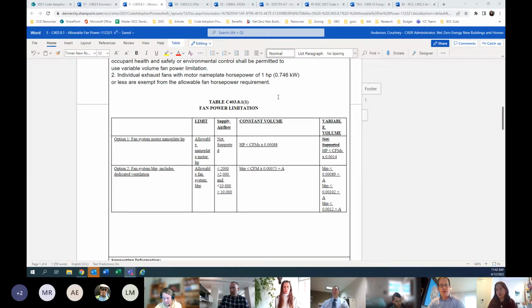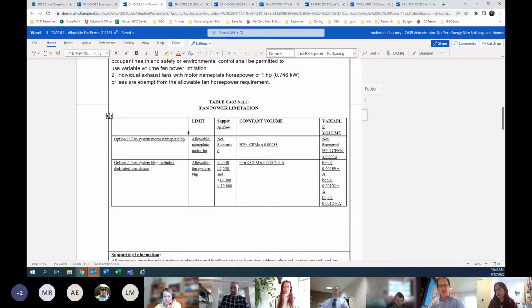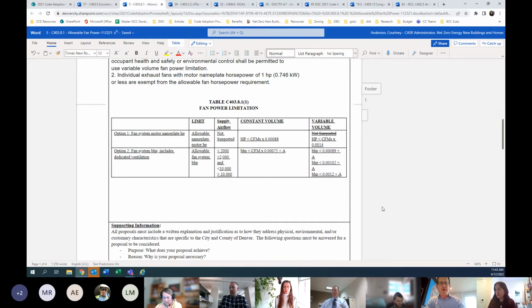So there's still two options. One is just the nameplate horsepower option 1, and there's the allowances there for constant volume and variable volume, and then option 2 is based more on the actual brake horsepower calculation, so the actual duct layout for the building. We have different allowances for variable volume systems. Recognize that the larger systems might have a different need than smaller systems. So based on the supply airflow of less than 2,000, which roughly corresponds to 5 or 6 tons of capacity.